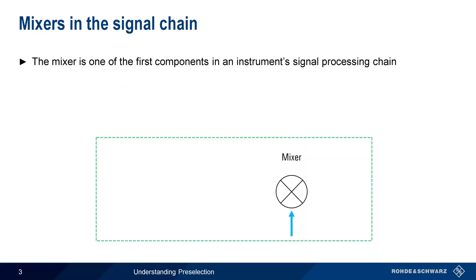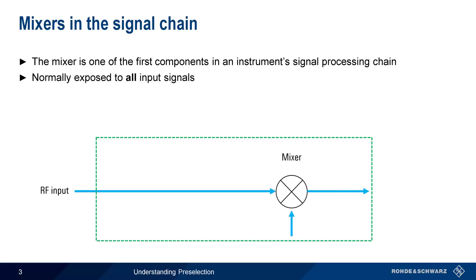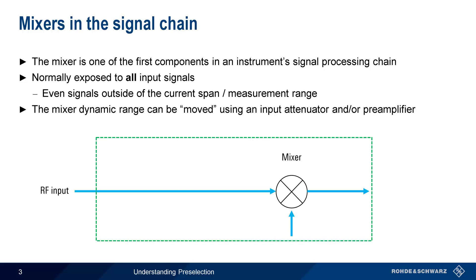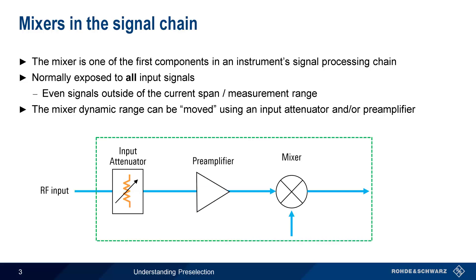Since the mixer is usually one of the first components in an instrument's signal processing chain, it's typically exposed to all signals present at the RF input. Even if we set our measurement range or span to only a limited frequency range, say 30 to 1,000 MHz, the mixer will still be exposed to RF power outside of this frequency range. In many instruments, dynamic range can be changed using an input attenuator and/or a preamplifier to raise or lower the input signal level. So why are we so concerned about protecting the mixer? There are really two main reasons: compression and spurious mixing products.